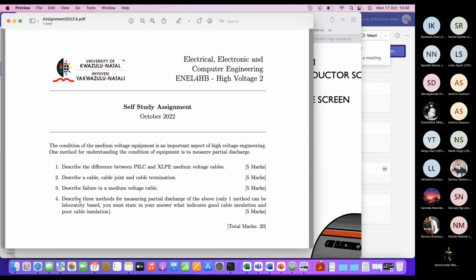A cable joint, so often around Durban, you get faults because we've got a big cable network here, and they dig up the ground and they go there and they join two cables together. They remove the faulted bits, they join two cables together. So that joint has to be better than the cable, has to have better insulation than the cable. So it joins the cable, then you've got to insulate that joint, then you've got to protect that joint. So it's very important to get that joint correct.